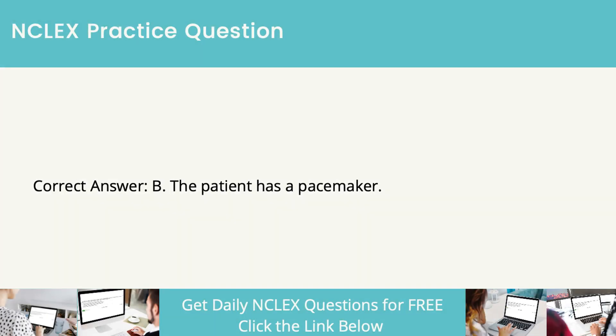The implanted pacemaker will interfere with the magnetic fields of the MRI scanner and may be deactivated by them. Patients with cardiac implantable electronic devices (CIED) are at risk for inappropriate device therapy, device heating or movement, and arrhythmia during MRI. These patients must be scheduled in a CIED-blocked slot or with electrophysiology nurse or technician support. Nowadays, MRI-conditional cardiac implantable electronic devices are widely available.